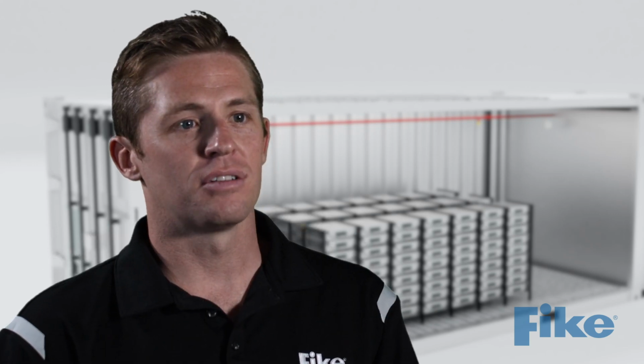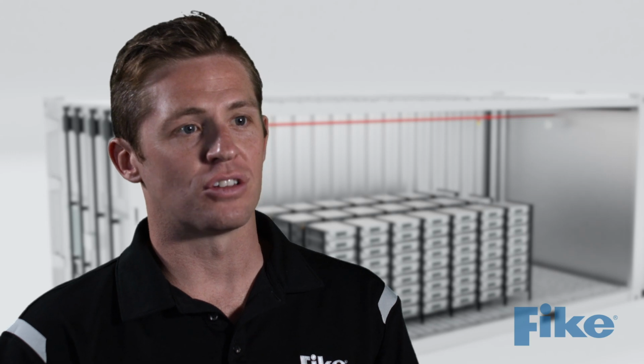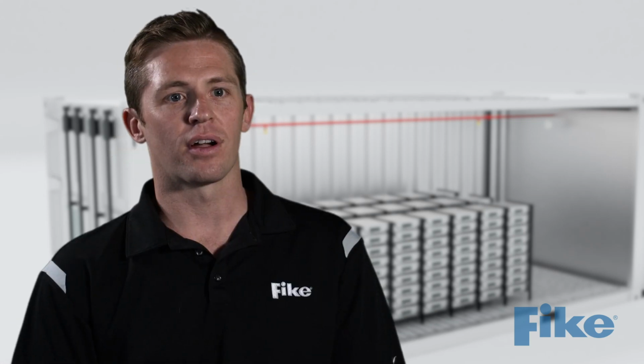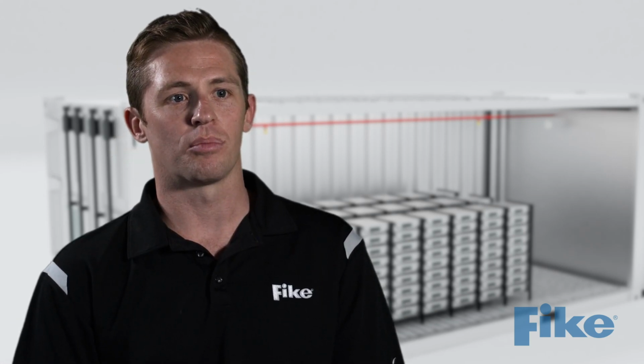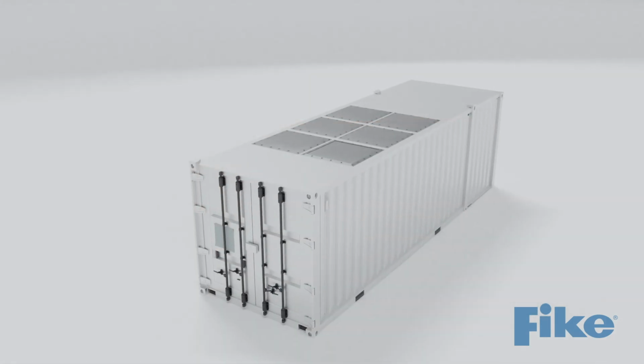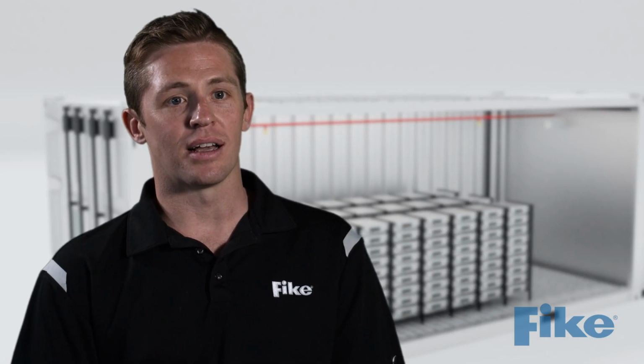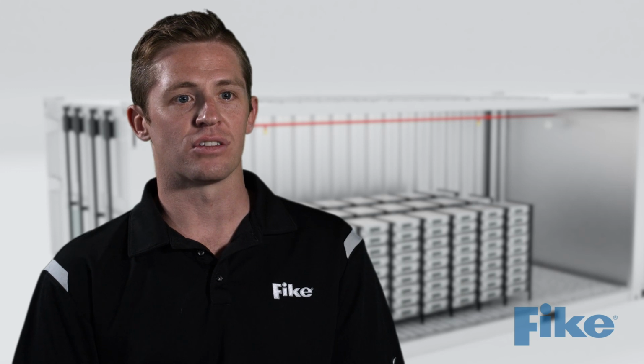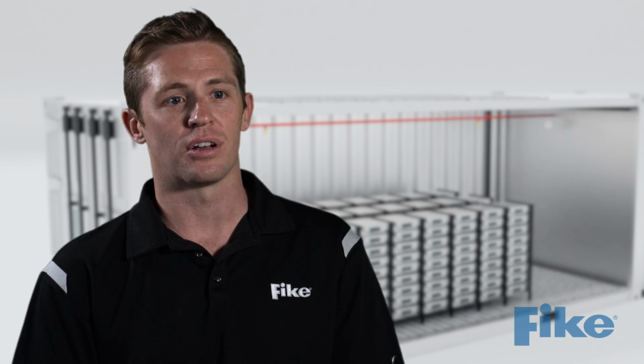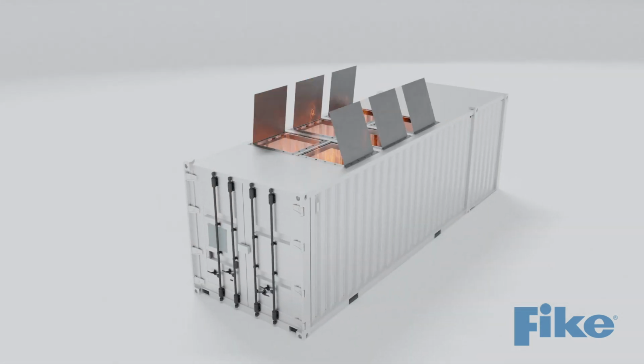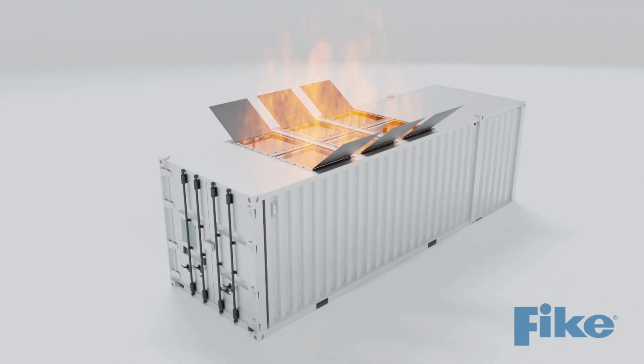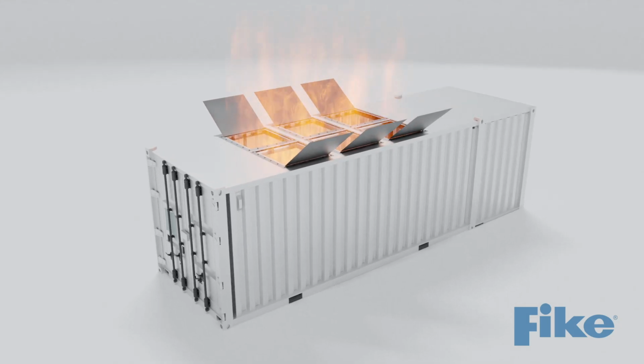Various layers of protection may be used to prevent a battery energy storage system from exploding. Fike recommends that all BESSs are protected with explosion vent panels. If a deflagration occurs within a BESS container, the explosion vents installed on the top of the enclosure will burst at a predefined low burst pressure, releasing the pressure and flames upward, thereby preventing an uncontrolled rupture of the vessel.